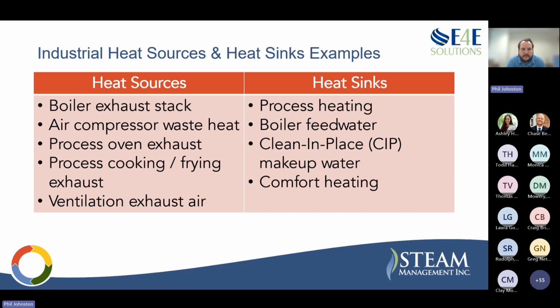On the sink side, it's heating applications in the process or inflows to a utility that have a heating component to them. Boiler feed water is a very common place to use this. Also, CIP or clean in place, if you're not familiar with the acronym, that's all the cleaning water, especially in food and beverage and other industries like that. Cleaning is a huge part of the heating load for the plant. So that's a really big heat sink.